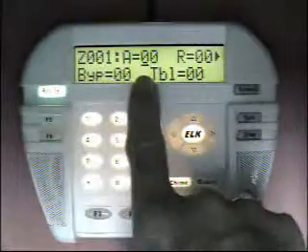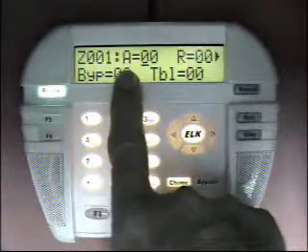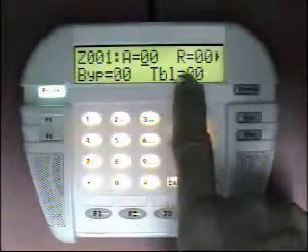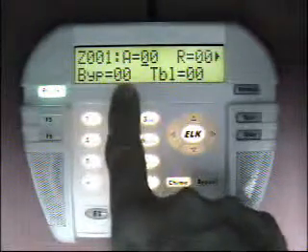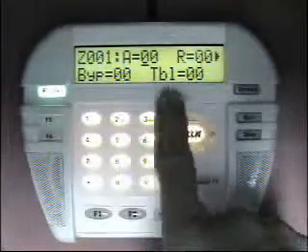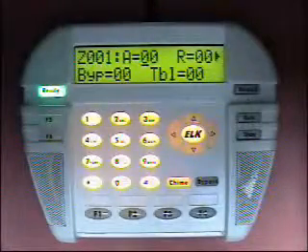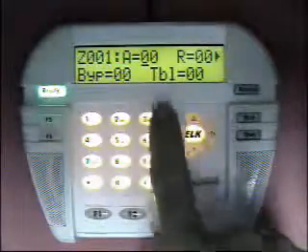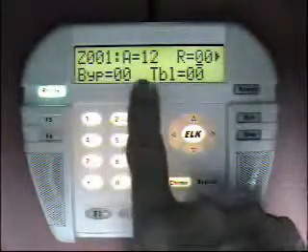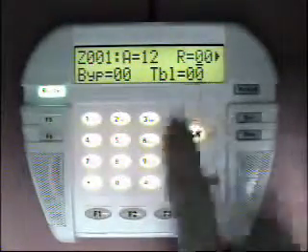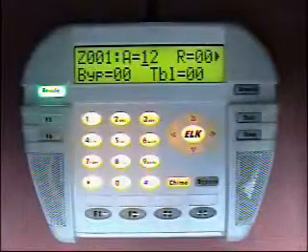When you type it in, the cursor moves over to the first position. The A means this is the alarm reporting code. The R means this is the restoral reporting code. The BYP means this is the bypass reporting code. And the TBL means this is the trouble reporting code. Each reporting code has two digits and you must enter both digits — for instance, 1, 2. The cursor moves on to the next position. If you want to go back and edit that, hit the left arrow key to move back into position.